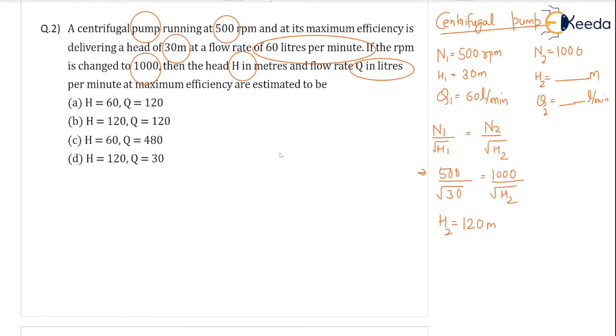And for calculation of discharge, we are having the relation q1 by root h1 equal to q2 by root h2. And the value of q1 is 60 liters per minute by root h1 which is 30 equal to q2 unknown value h2 which is already calculated 120. So your q2 is coming out to be 120 liters per minute.